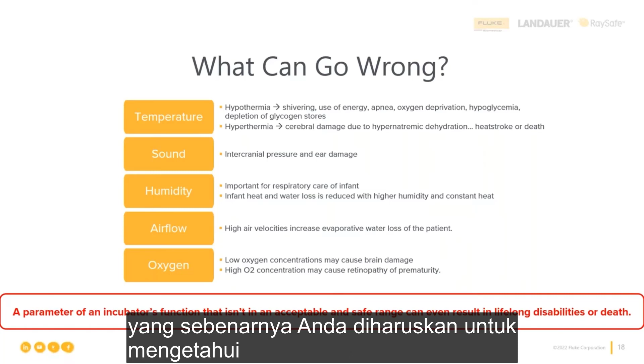So as we talked about throughout this webinar, an infant's first few days of life can be their most critical, right? So with that, we would like to make a point that it is important to routinely test and verify the safety and performance of infant incubators, and adopt a consistent inspection frequency for those incubators. You can check the manufacturer's service manual of the incubator for the frequency recommendations and see what they suggest there. The FDA, along with most manufacturers, recommends a minimum inspection frequency of once per year for the incubators.